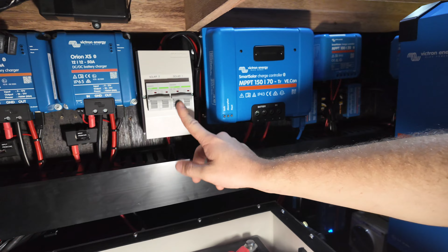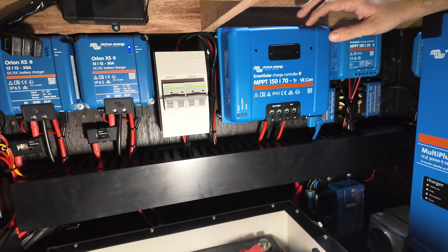Main switch for both solar arrays. The bigger one, solar array 1, is putting in anywhere between 50 to 60 amps on a good day. It's 5 by 225 watt panels on the roof, so there's a lot of juice up there. Because the solar string is larger than 3 panels per string, he has to have a fuse on every solar panel, which we've done, but it's on the roof underneath one panel. So if it ever needs to be accessed, you just need to take up one panel.